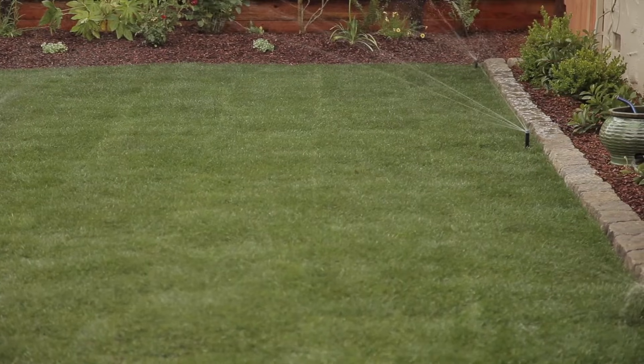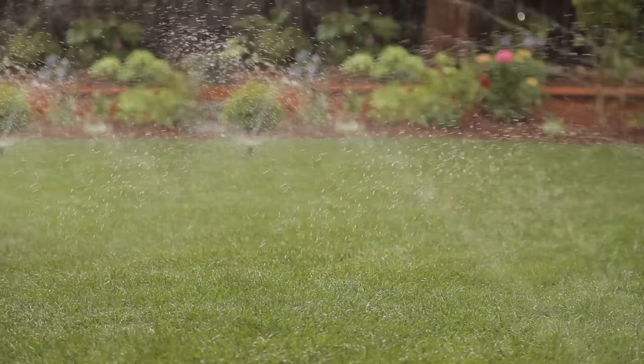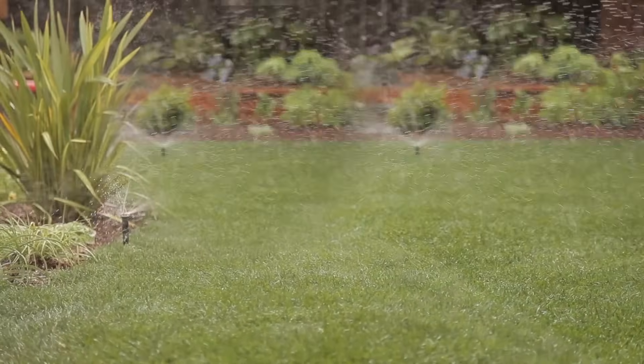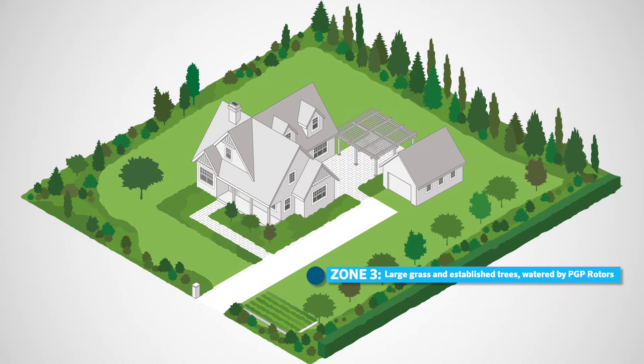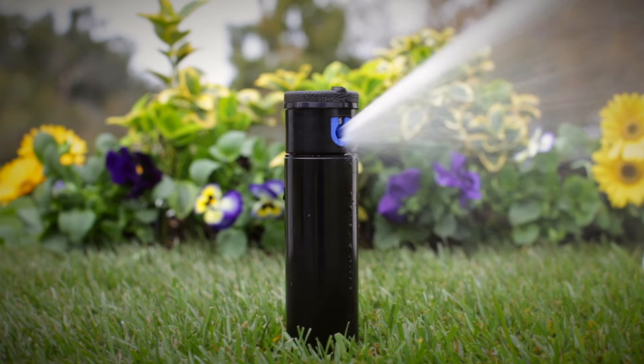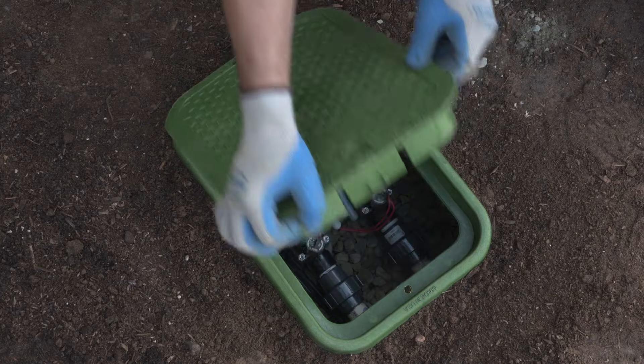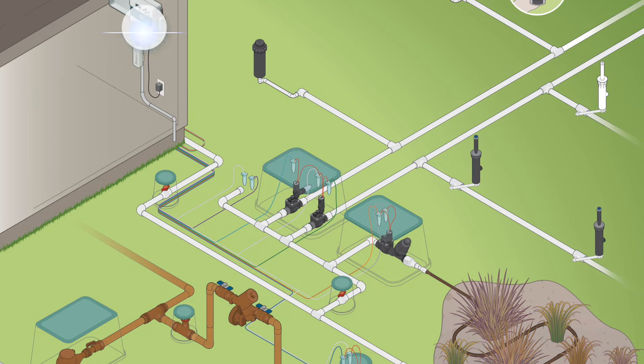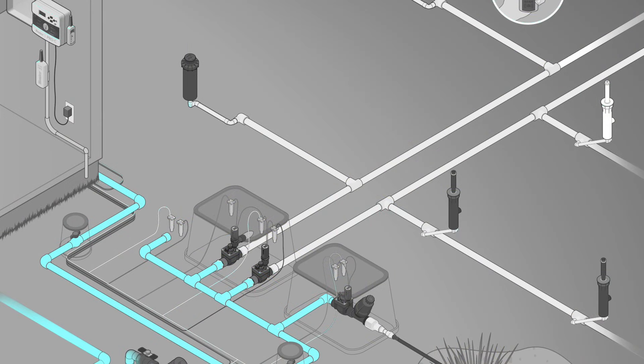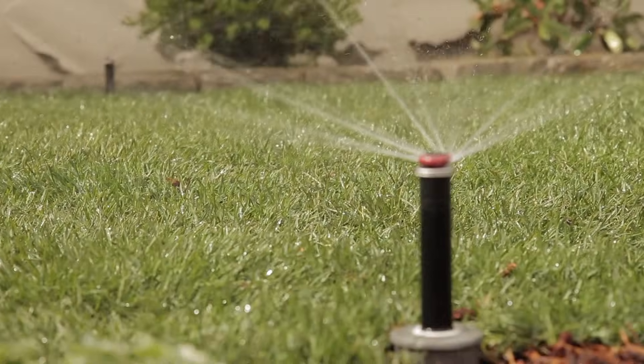It's important to note that no other sprinkler types are being used with the MP rotator, and only similar plant material is being irrigated. This is an example of a station with proper hydrozoning. A hydrozone is an area of similar plant material being irrigated by the same type of emission device. Station Three is an example of a gear-driven rotor zone. You'll want to use the same brand and type of rotors and select the proper nozzles. To activate any of these valves, a 24-volt AC electrical signal is sent to the valve from the irrigation controller through a set of station control wires to open the valve solenoid, allowing water to flow through the lateral lines to the sprinklers or irrigation devices.